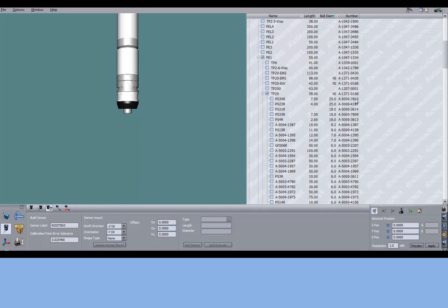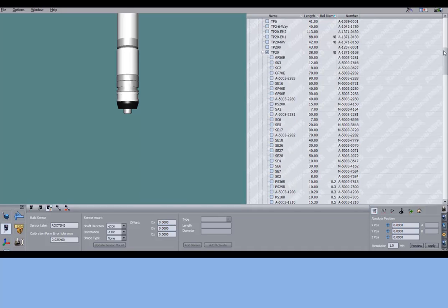If you click on it, you can see this is like a standardized window sorting functionality. So now it starts from the largest ball diameter and descends down. But what you typically need is to go the other way. So first you see all these blanks. That means these are extensions. And then the next thing is you want to look at the extension, how long physically you have in your probe.